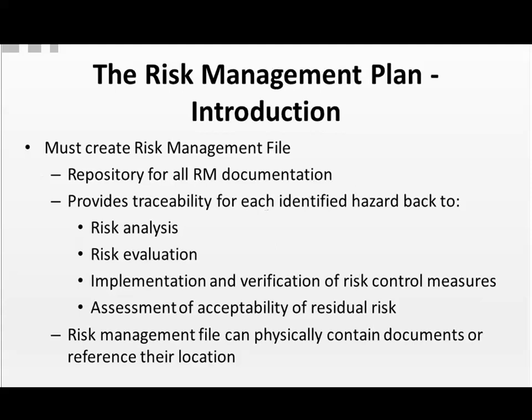It provides traceability for each identified hazard back to the risk analysis, the risk evaluation, implementation and verification of the risk control measures that were applied, and assessment of the acceptability of residual risk. That risk management file can physically, as I said, contain the documents or simply contain a reference to where they can be located.